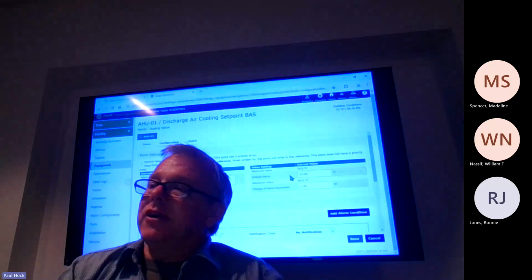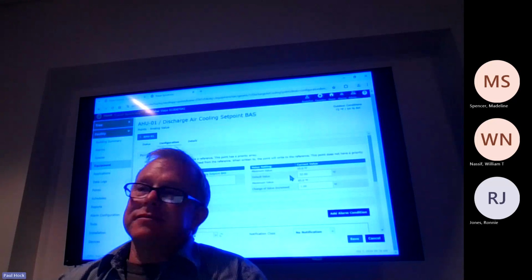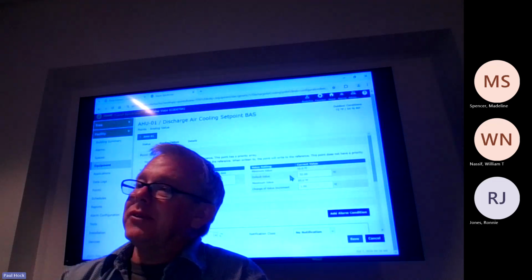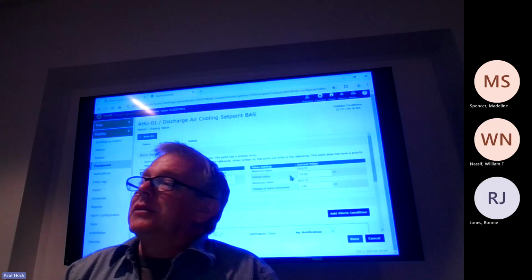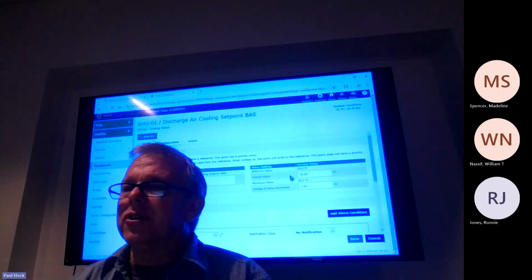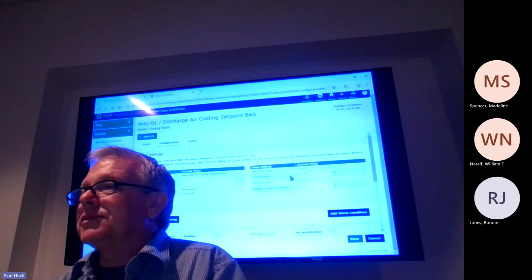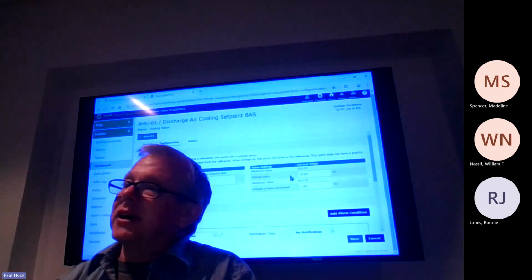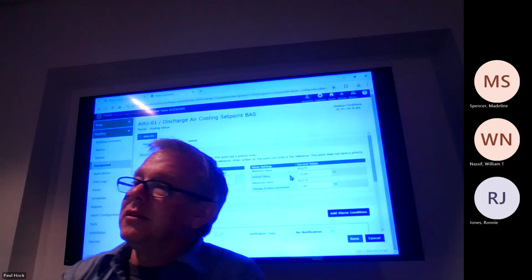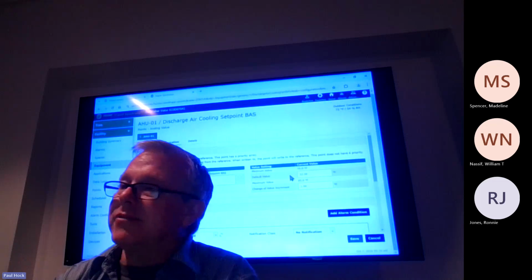If you're continuing overriding points, what can happen is if something happens, like a power failure, those overrides can be released. As soon as it powers back up, the system's going to automatically power back up by itself and immediately go back to default. If you change it, I think it's within 2 hours. If you change the set point and the system fails from power failure or something like that and it reboots, it's going to go back to its default value. Generally, anything after 2 hours, it's going to maintain your override. But anything's possible. Like I said, the power surge can always scramble it and it's going to go back to default value on everything.